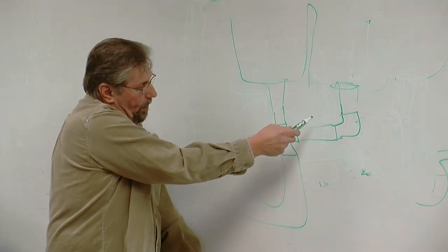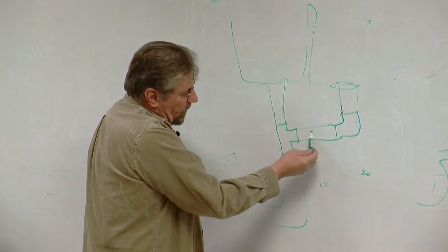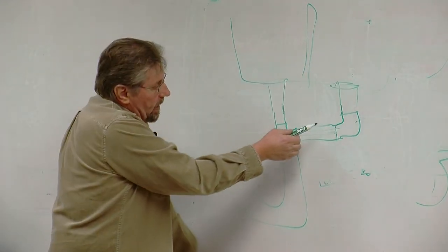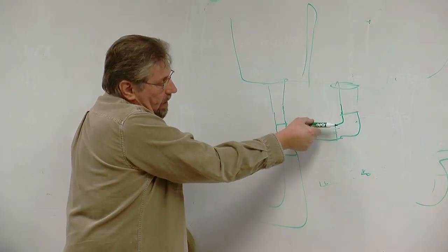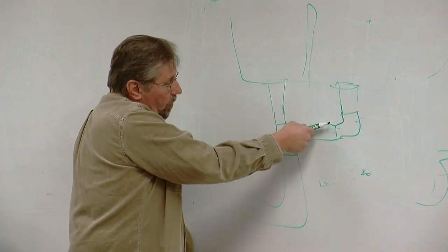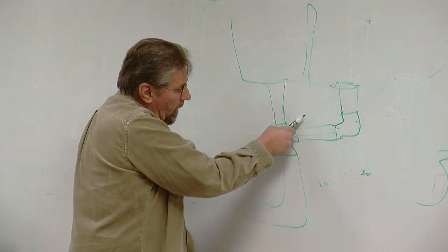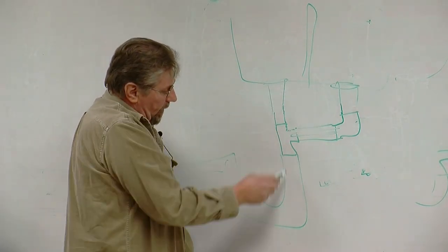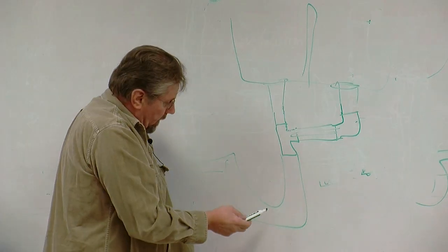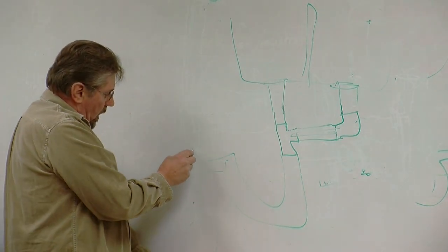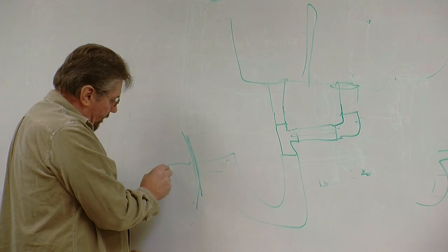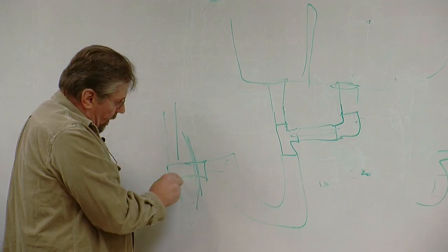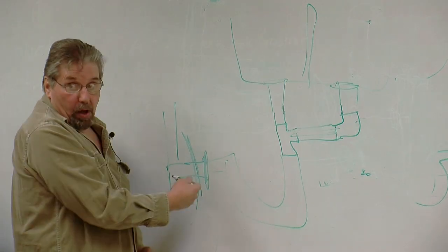So what happens is this pipe here, the angle of this pipe, again, 1/4 inch per foot. If it's leaning back, then stuff can build up because it can't get out. So you kind of inspect it to see that everything is falling 1/4 inch per foot, all heading toward the drain. Now, typically on this kind of situation, if you need to snake this, you're better off to, where this goes into the wall, you're going to have a fitting here, probably maybe a vent too, but this will stick out, and this is where you have a nut on it, where it goes into the wall.